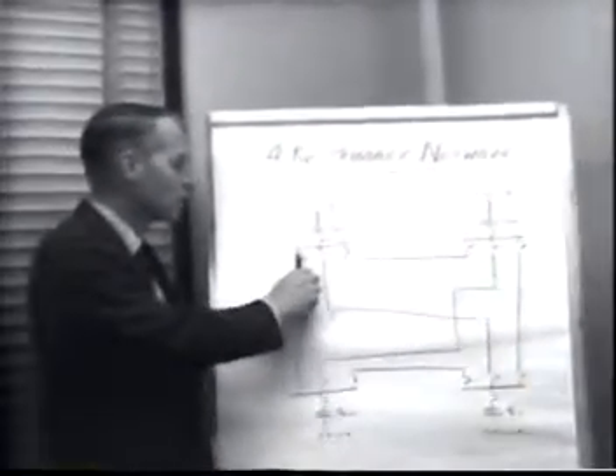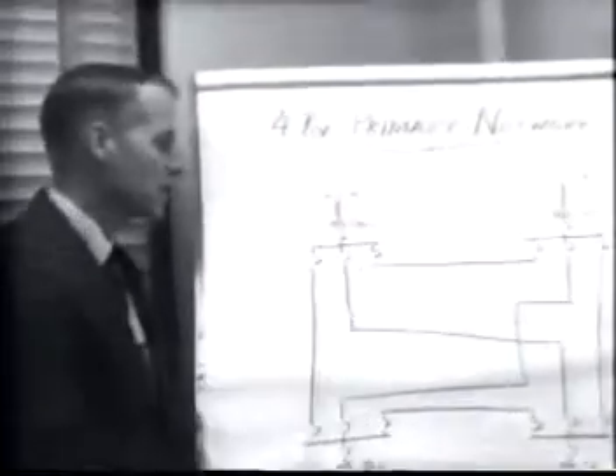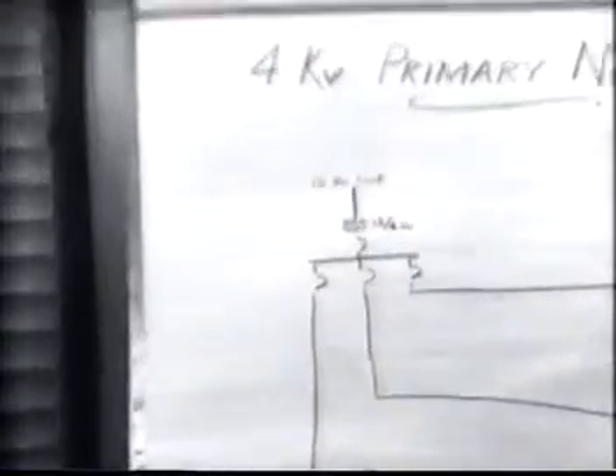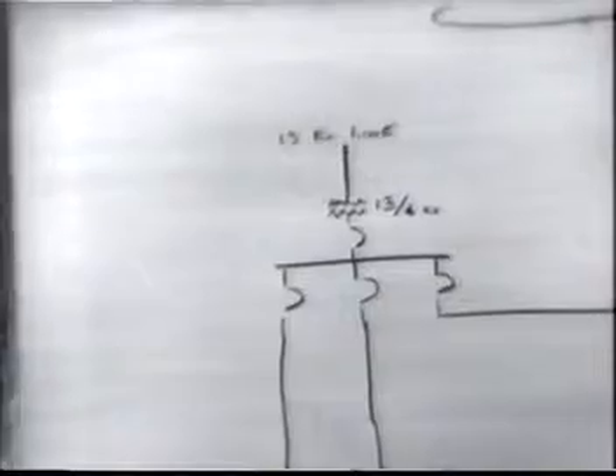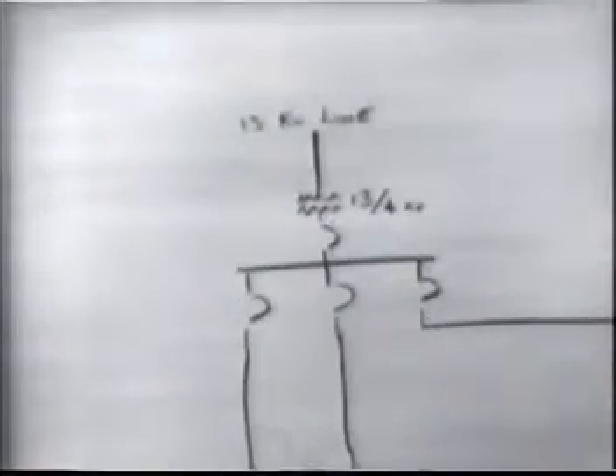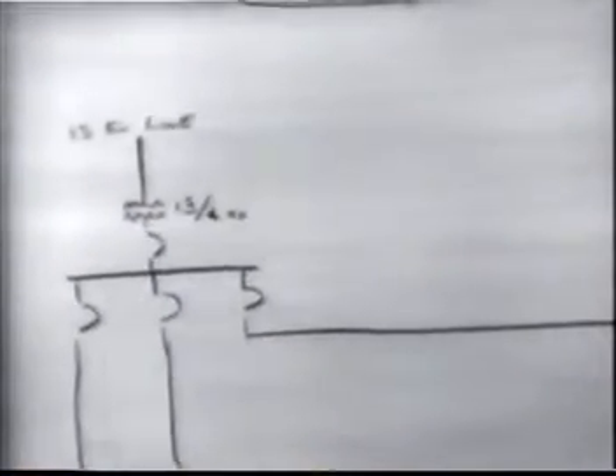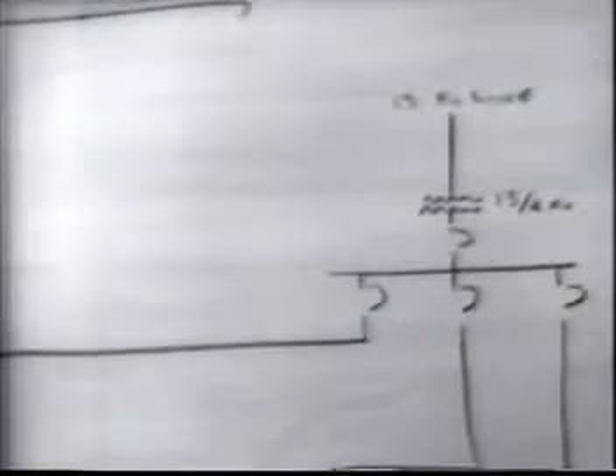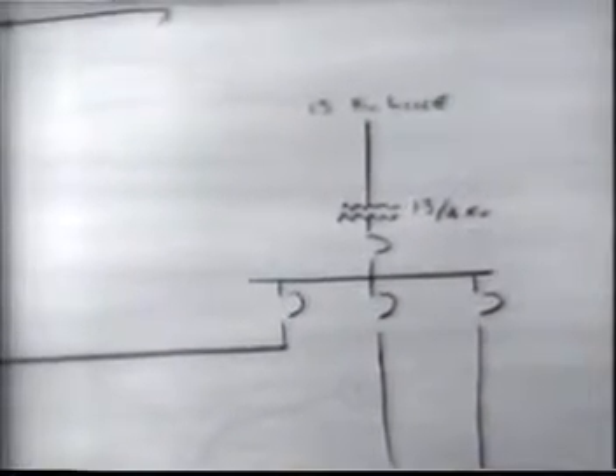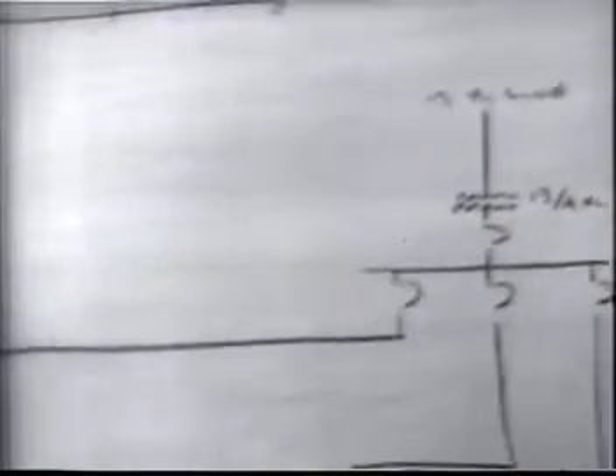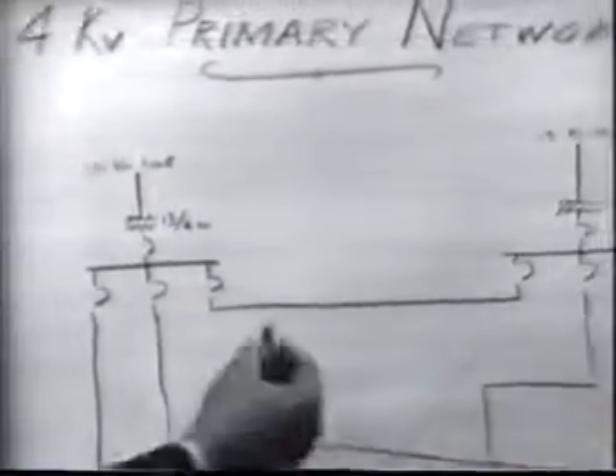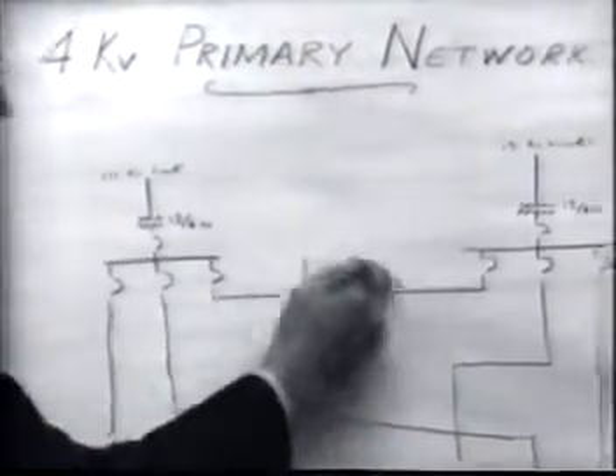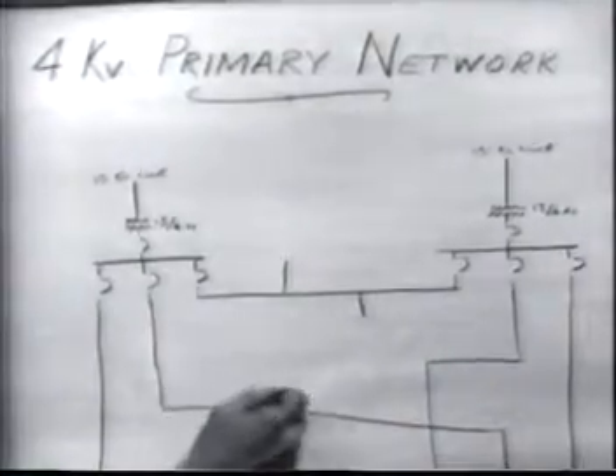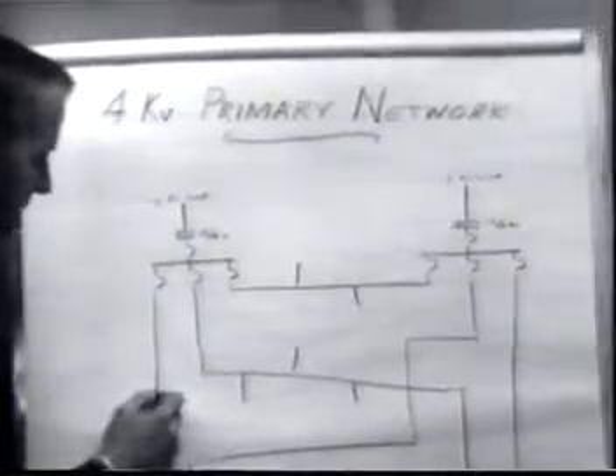The substations that we installed here, called unit substations, used air circuit breakers. We were among the first utilities in the country to use air circuit breakers both at 4 kV and 13 kV to any great extent. So you can see that from these tie lines we would have circuits going down the alleys and down the streets to feed the residential customers.